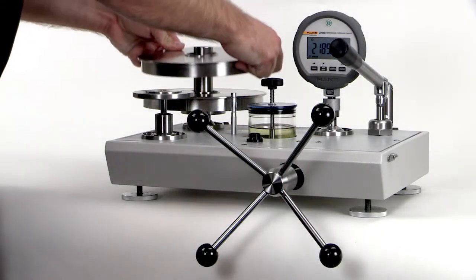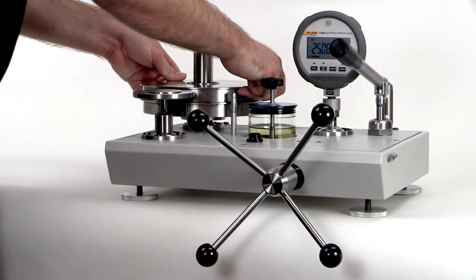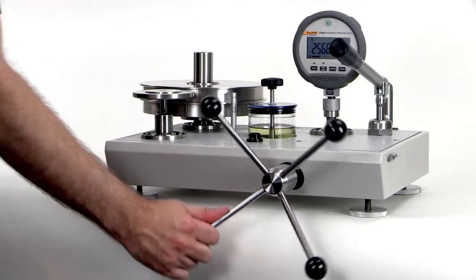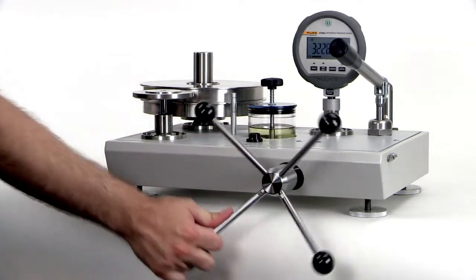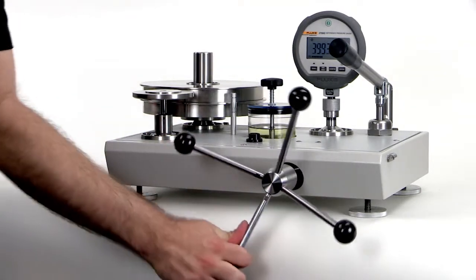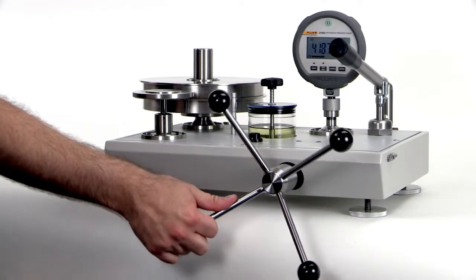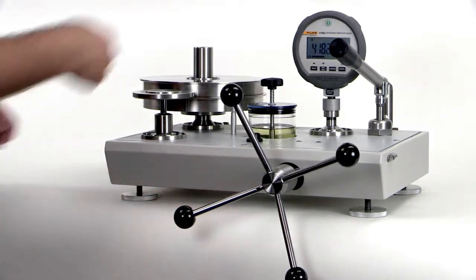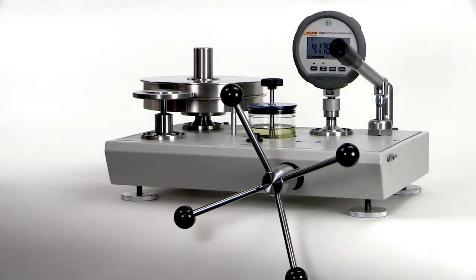Certain steps were taken in the design and manufacture of these deadweight testers to ensure that this specification can be met without additional calculations by the user. At the time of manufacture, the amount of mass required to generate a given pressure at the customer's gravity is calculated. The masses are then trimmed to this value.